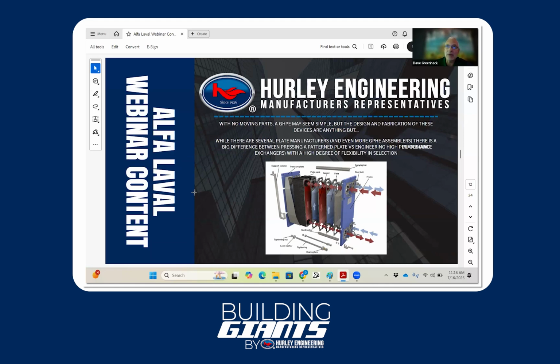And if you're running it at 40, 45, 50 degrees, no problem. But now you've got air to water heat pumps, and it becomes a big problem in heating mode. And they'll scale up till they become a brick. Some folks don't even notice it until it's too late, and you're tripping out on high head on the heating mode, or on the water side, you might be doing a low pressure trip on the evaporator.